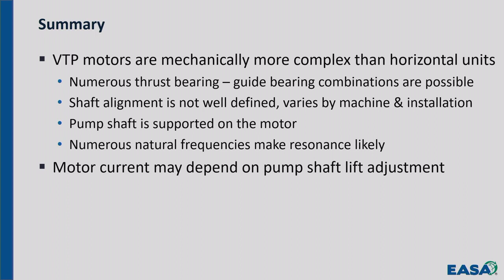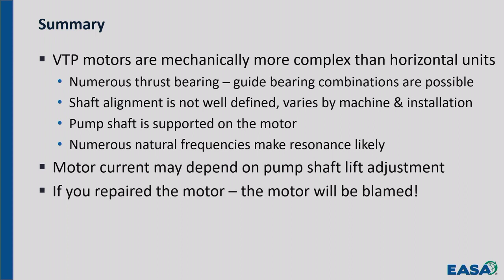And if you repaired the motor and there's a problem, it must be the motor, right? The problem could be the pump. The problem could be the structure. The problem could be the head and flow on the pump. But, oh no, you fixed the motor. It's got to be a motor problem, right?